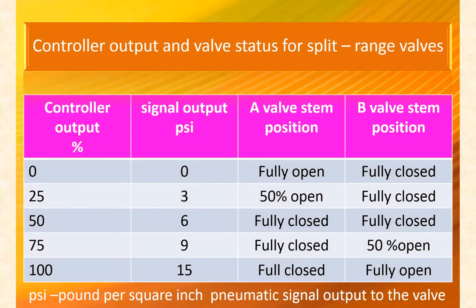This table presents the controller output to the two split range control valves and their response. At 0% controller output: A valve fully open, B valve fully closed. At 25% output: A valve 50% open, B valve fully closed. At 50% output: A valve fully closed, B valve fully closed. Note: at 50% output, both A and B are fully closed.